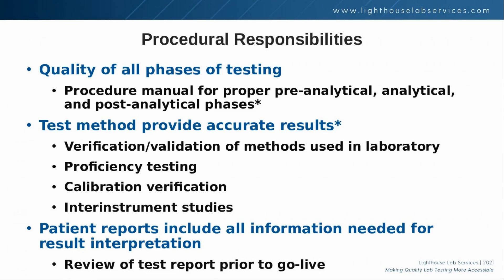A large portion of the procedural responsibilities are to make sure that the test methods used in the laboratory can provide accurate results. The first step in this process is either the verification or validation of the methods performed in the laboratory prior to patient testing. In addition, accuracy can be assessed throughout the year by proficiency testing, calibration verification if applicable, and inter-instrument studies if the laboratory is using more than one of the same instrument for the same test.